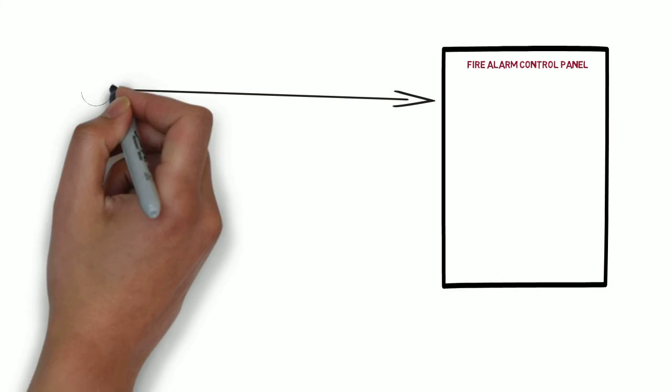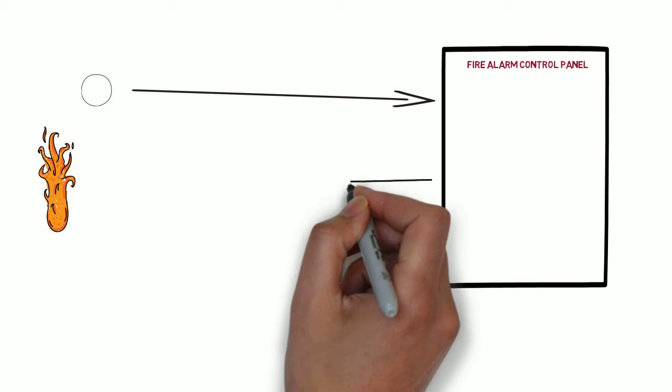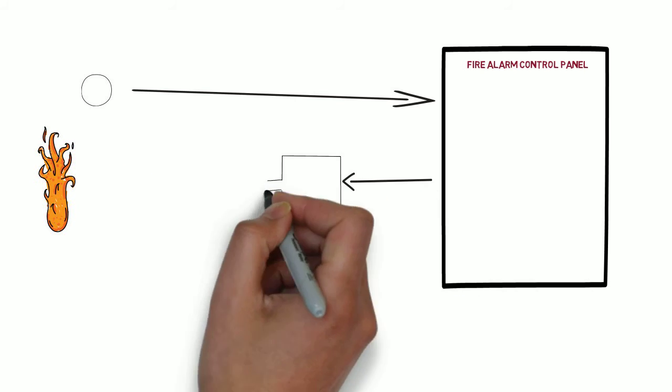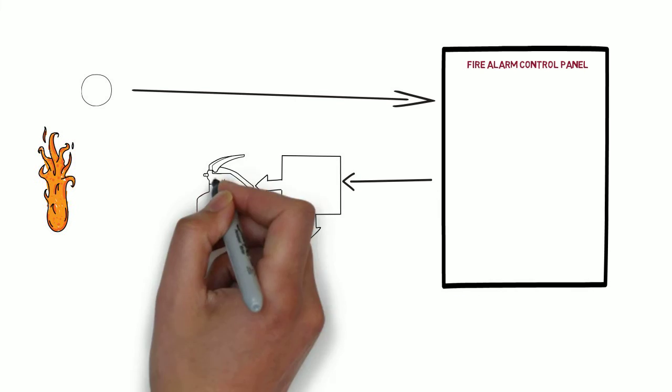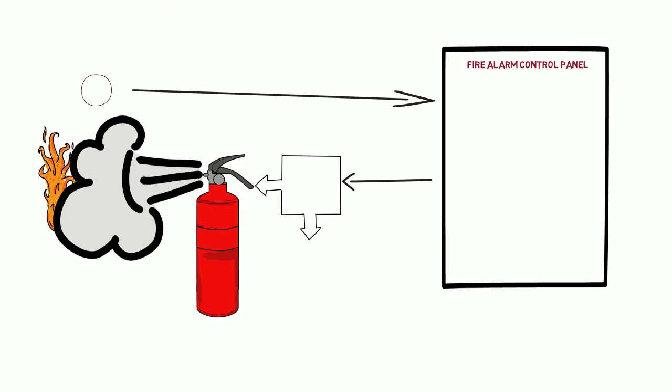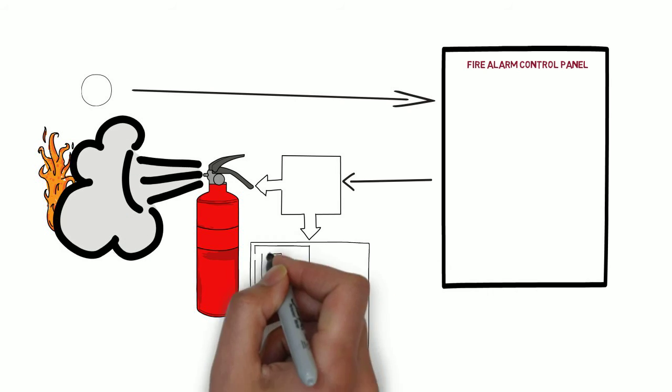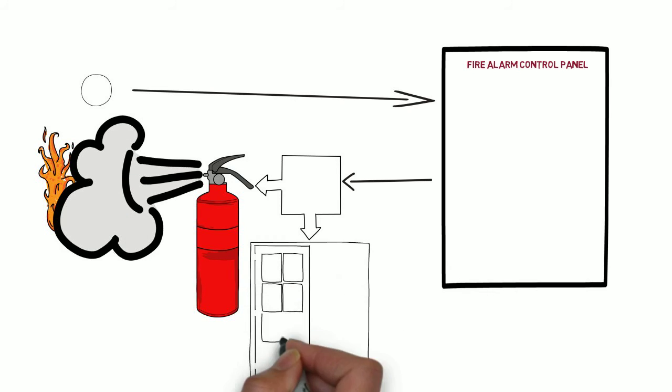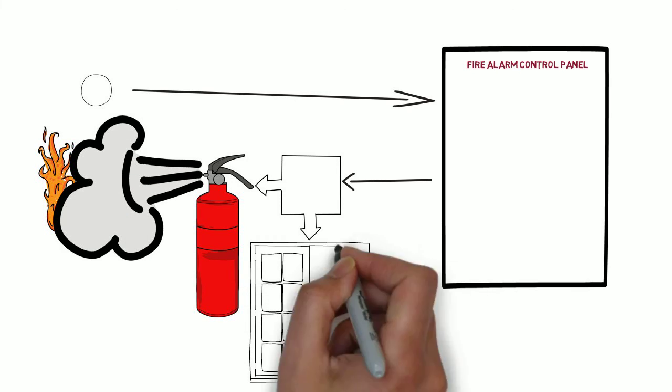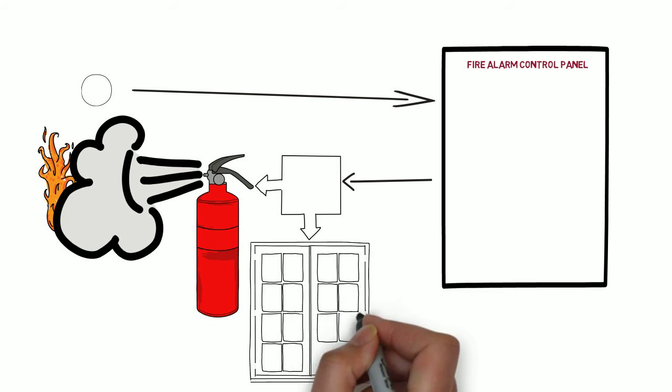A control unit that releases an extinguishing agent upon the detection of a fire alarm condition is a releasing service type. It is also for control units that release non-extinguishing and non-water based, such as releasing fire doors.